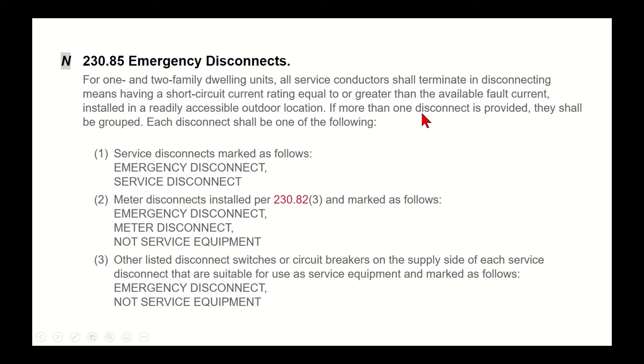If more than one disconnect is provided, they shall be grouped. For one or two family dwellings, all service conductors shall terminate in a disconnecting means — not a service disconnecting means — and that disconnecting means has that short-circuit current rating and has to be located outdoors, readily accessible. If more than one disconnect is provided, they shall be grouped.